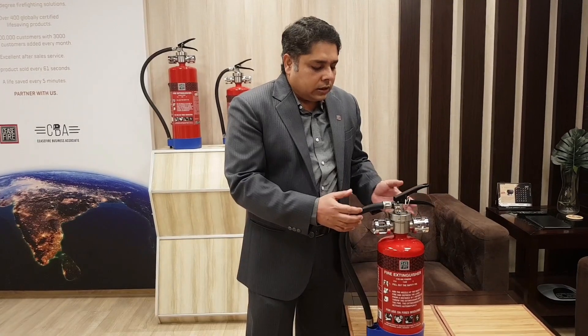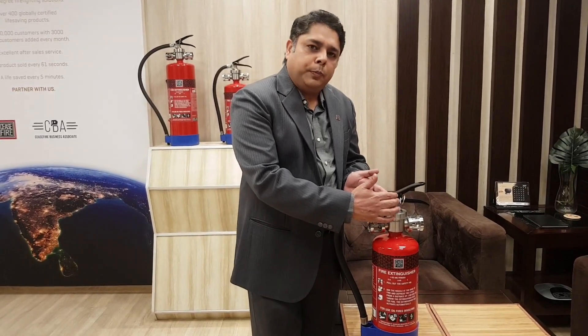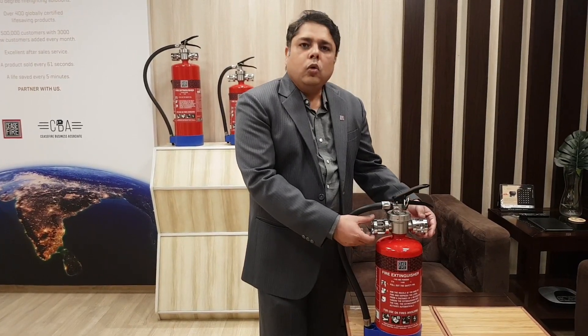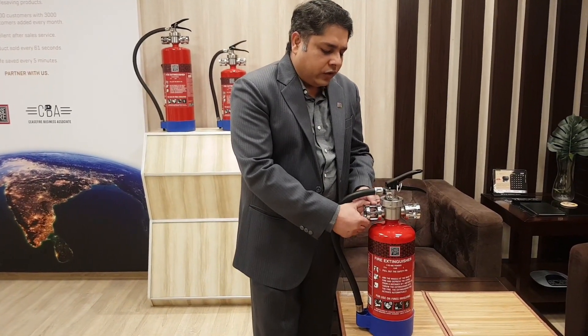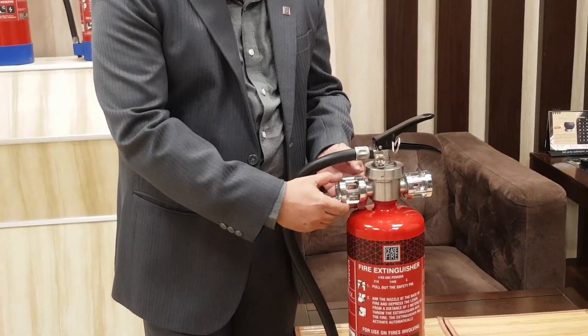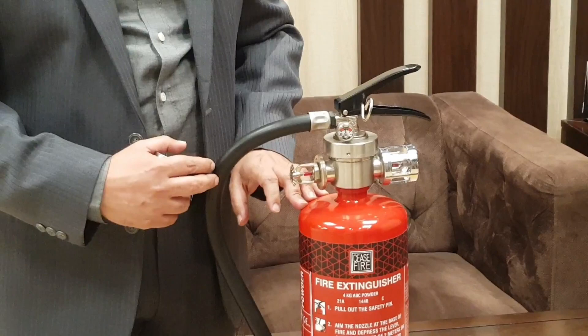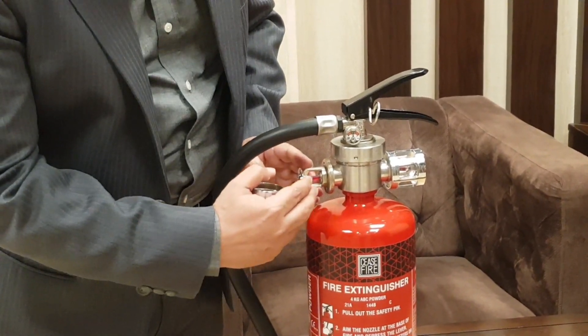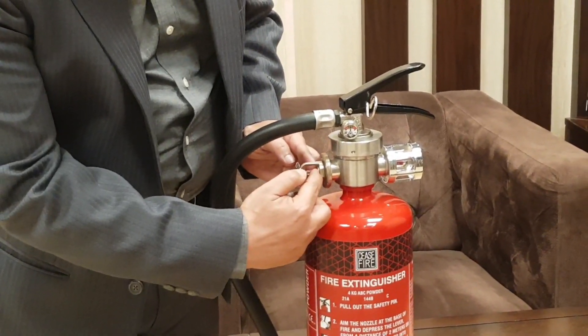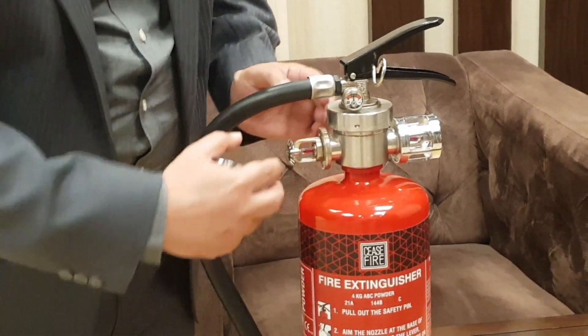The other difference is you have a specialized valve on top of the cylinder which has the conventional usage pin, and it also has a chamber to which two sprinklers are attached. These sprinklers are fitted with a quartzoid bulb, designed to burst open at 68 degrees centigrade. In case a fire comes in close contact with the extinguisher, this bulb will burst open, the pin will be removed, and the extinguishing agent will come out.